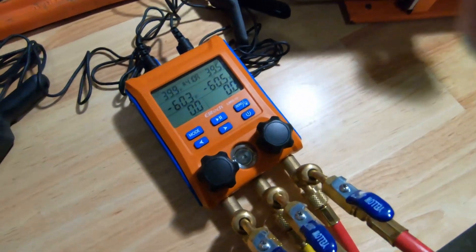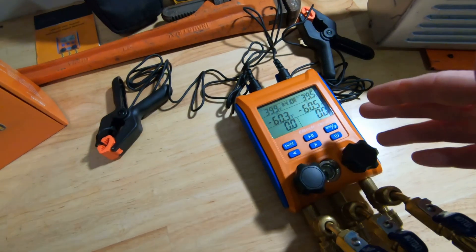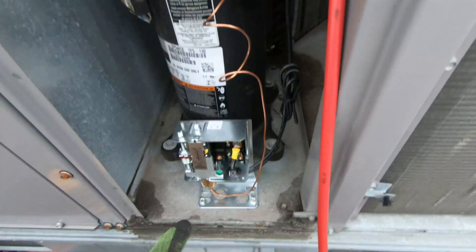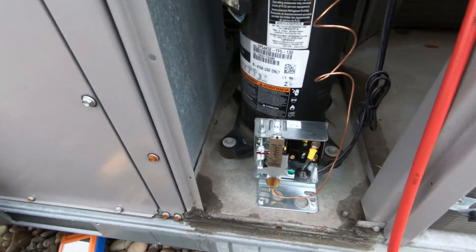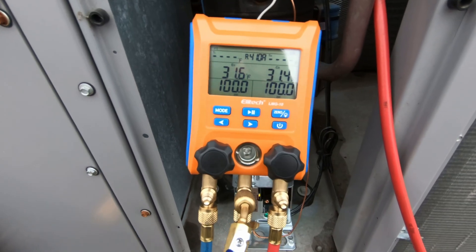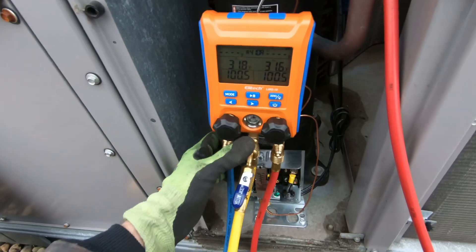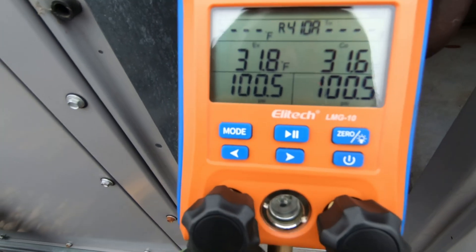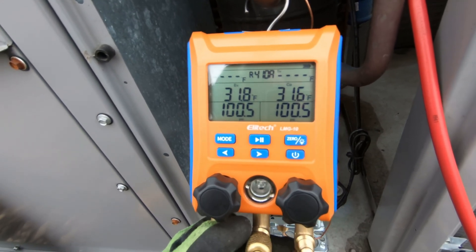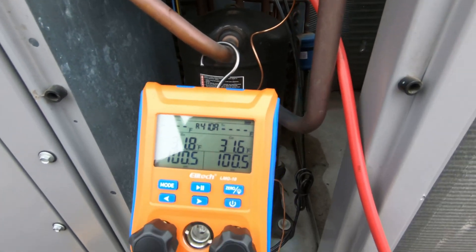I was a little leery to accept these but I've been pretty happy with them so far - used them on a couple of jobs. All right, I'm here doing a high pressure switch and a fan cycle switch on this Carrier unit. I wanted to show you the new manifold set that Elitech sent me - it's the LMG-10, pretty slick. I've got it hooked up here just so I can test this fan cycle switch. I'm set on 410A, I've got 100 pounds of standing pressure.